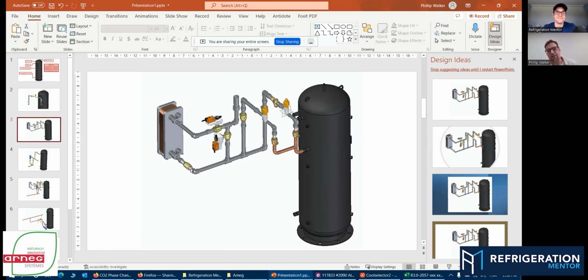We got a check valve over here, and this is what's really important in CO2 systems. When we do a lot of speaking on CO2, I think when we're training in front of the machine, the common question is typically insulation and check valves. Gas wants to migrate. CO2 wants to migrate. So any type of circuits that you're working on, and you believe that they're going to become pumped out, or we call them dead circuits, that you're not going to be using throughout that certain time of the year, really consider, if they don't have one, a check valve, because gas is going to migrate.